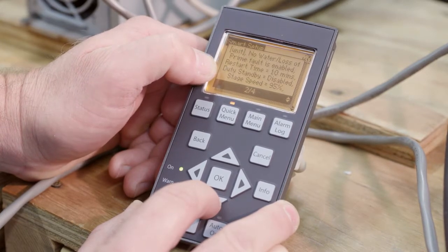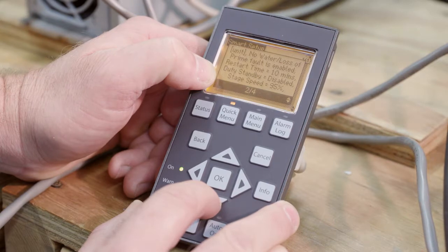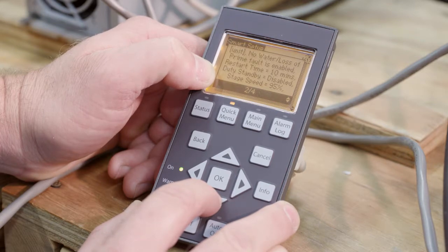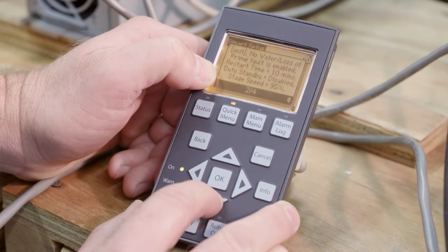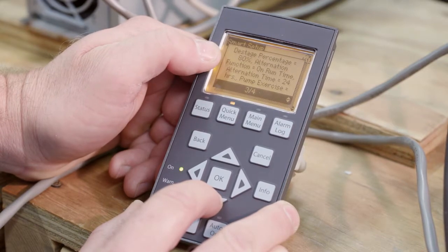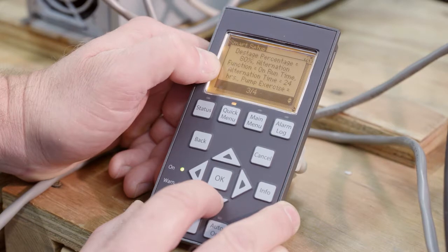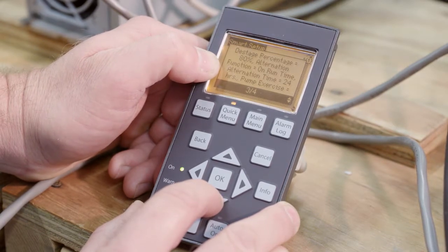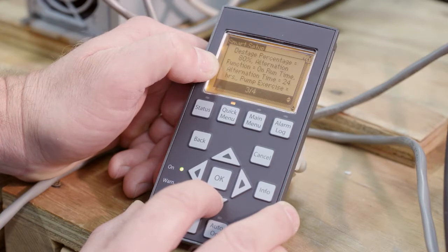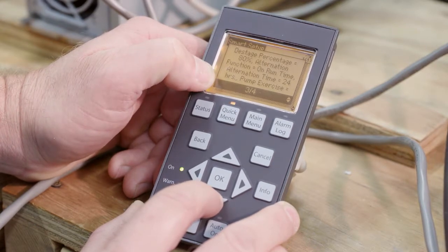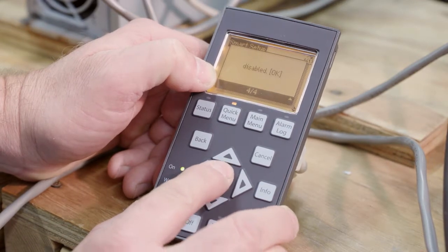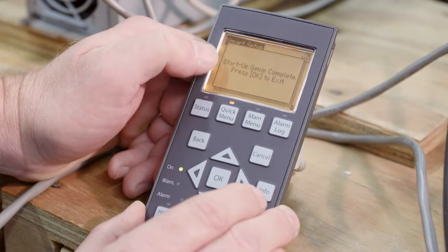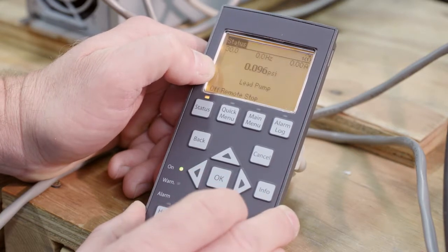No water loss of prime fault is enabled, and that's restart time of 10. Duty standby disabled. Stage speed. So now it's getting into, because we chose multi-pump, your staging and destaging. So we've got a 95% stage speed, a destage of 80. Alternation function is on runtime. So another new enhancement is you could change your alternation to runtime and to clock time. So that's another new addition to the advanced platform. All right, so we keep scrolling down. Going to hit the OK button. And Startup Genie is complete, so press OK.